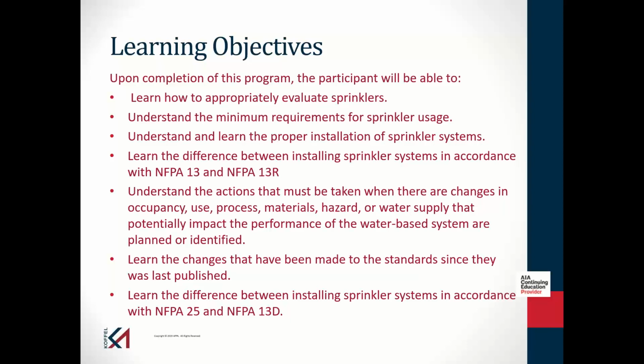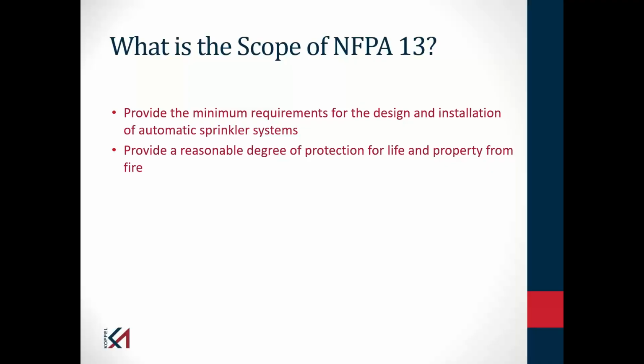And then the same thing with NFPA 25. You are probably in a jurisdiction that is using the 2014 or 2017 editions of those documents, and I'll identify some of the things that are in the 2020 edition of those documents. And then, going back, I tried to correct a typo on this and I did it incorrectly. Learn the difference between installing sprinkler systems in accordance with NFPA 13 and 13D. So above we talked about 13 and 13R, then we'll talk about 13 and 13D.